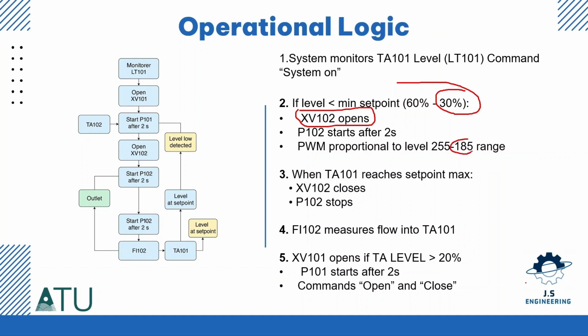So we start at 105 and then we raise until 255, and then when it gets closer to 60%, which is the maximum set point, it goes back down to 185. When the tank 101 reaches the maximum set point, the solenoid valve on the inlet will close and the pump will stop. The flow meters will measure the flow into tank 101, which is the main tank.